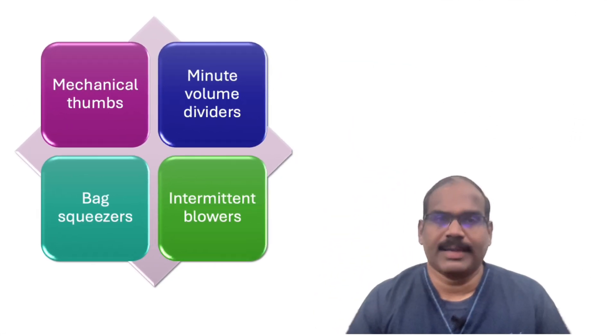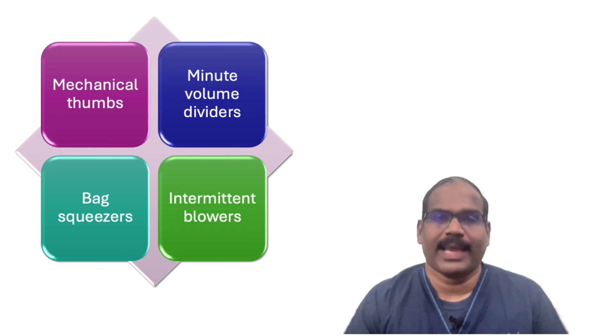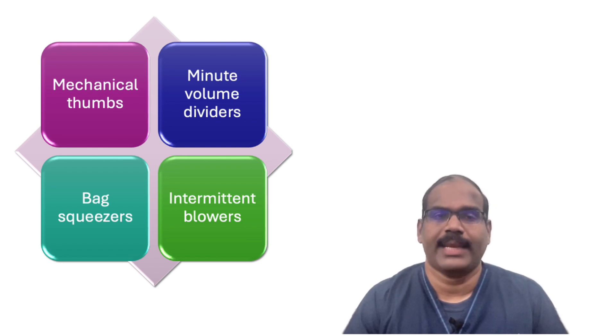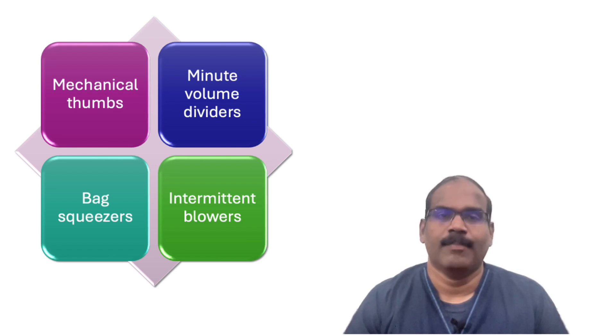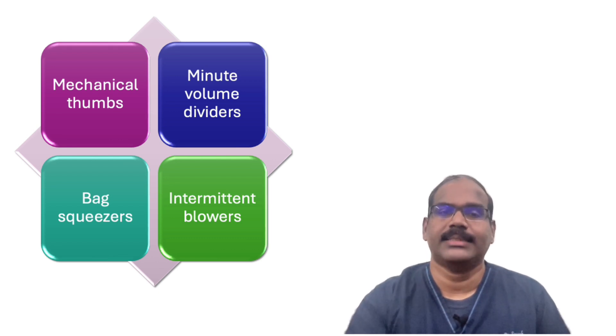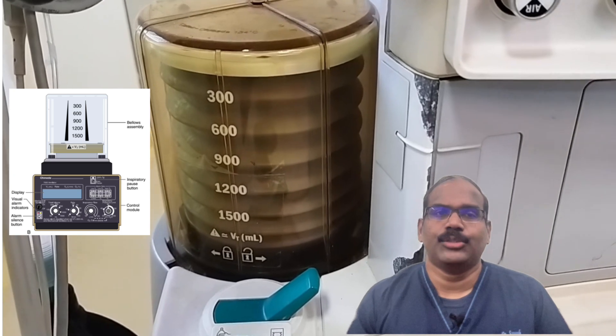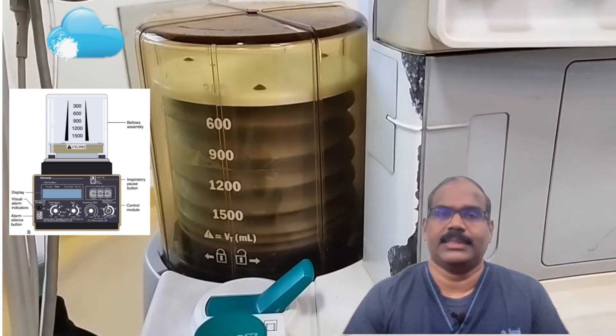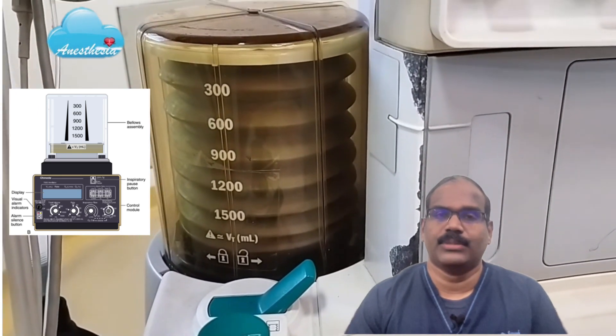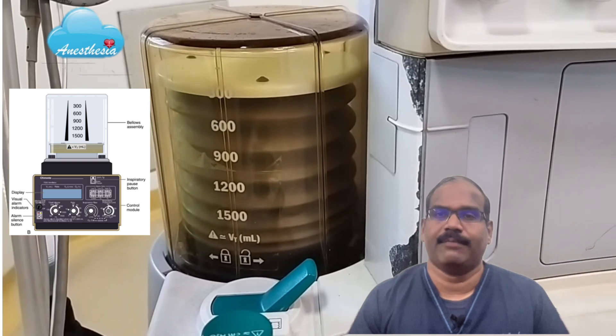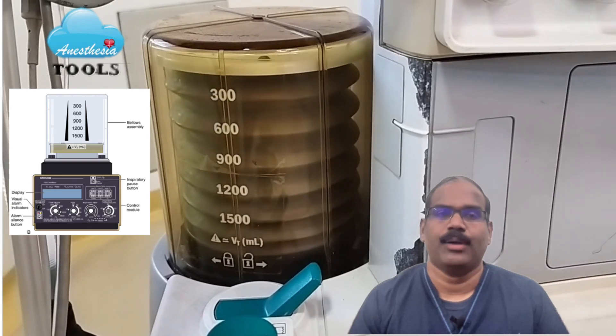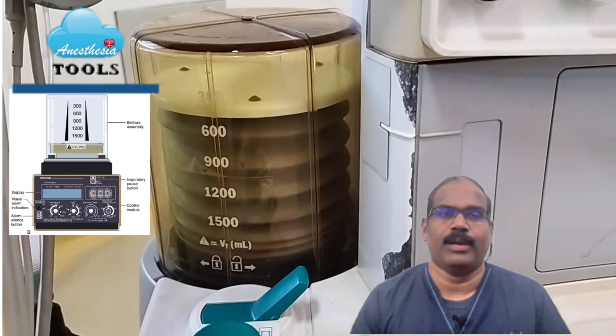Several methods of classification of ventilators exist. According to the mechanism of action, ventilators can be classified as mechanical thumbs, minute volume dividers, bag squeezers, and intermittent blowers. Moving into more contemporary anesthesia ventilators, based on the drive mechanism, we can classify them into bellows type and non-bellows type.